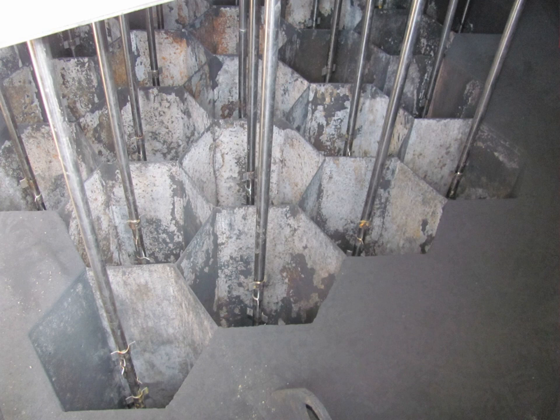ESPs continue to be excellent devices for control of many industrial particulate emissions, including smoke from electricity-generating utilities, coal and oil-fired, salt cake collection from black liquor boilers in pulp mills, and catalyst collection from fluidized bed catalytic cracker units in oil refineries, to name a few. These devices treat gas volumes from several hundred thousand ACFM to 2.5 million ACFM, 1180 cubic meters per second in the largest coal-fired boiler applications. For a coal-fired boiler, the collection is usually performed downstream of the air preheater at about 160 degrees Celsius, 320 degrees Fahrenheit, which provides optimal resistivity of the coal ash particles.